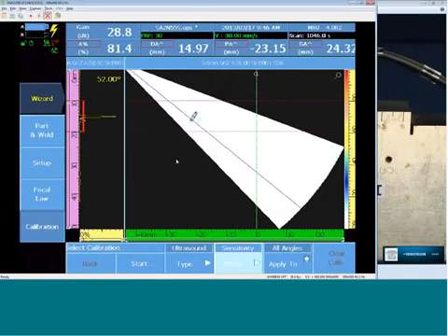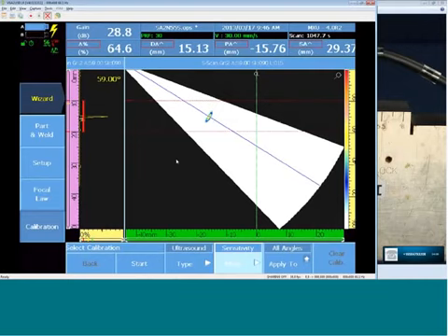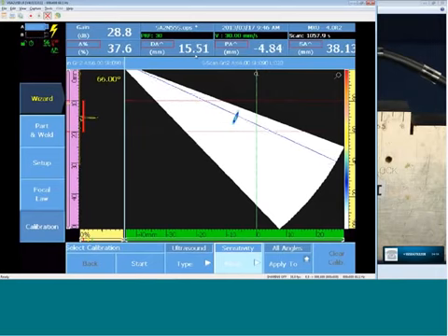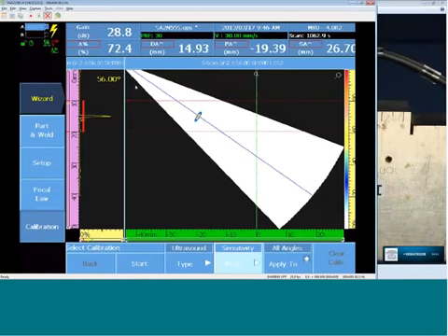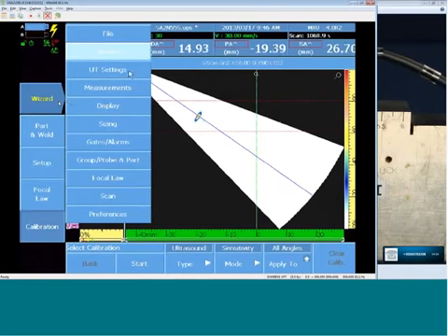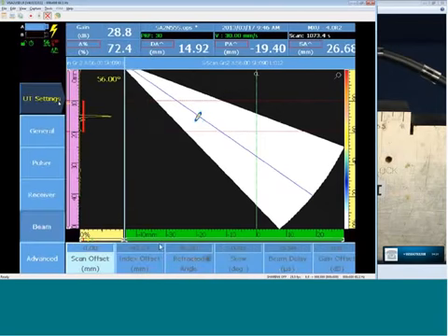What that tells us is that the software under Beam has calculated from the wizard our wedge delay correctly. I can perform the wedge delay function, maybe tweak it a little bit, but in accordance with the codes, in accordance with a conventional UT, my ability to verify this position prior to calibration verifies both the velocity of the wedge and the wedge delay that was calculated by the calculator.